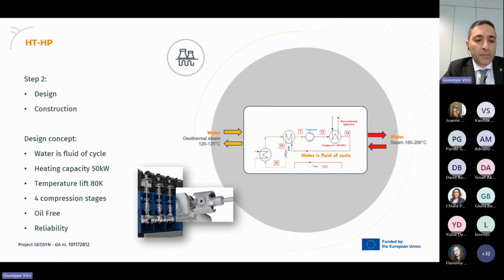The heat pump concept we showed before in the other presentation is the base for us; we need to follow a design with a capacity of 50 kilowatts in heating. We would like to have a lift of 80 Kelvin. We need 4 stages of compression, oil-free for the reasons shown before, because we use piston compressors, and it's very important to have a system with correct reliability. This is the range we showed before. We would like to increase the temperature; with a lift of 80 Kelvin, we would like to have steam around 180-200 degrees Celsius.